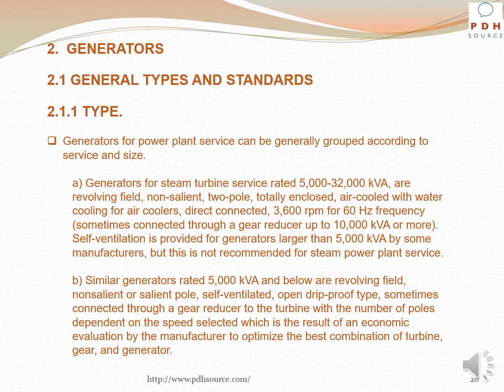Similar generators rated 5,000 kVA and below are revolving field, non-salient or salient pole, self-ventilated, open drip-proof type, sometimes connected through a gear reducer to the turbine, with the number of poles dependent on the speed selected, which is the result of an economic evaluation by the manufacturer to optimize the best combination of turbine, gear, and generator.